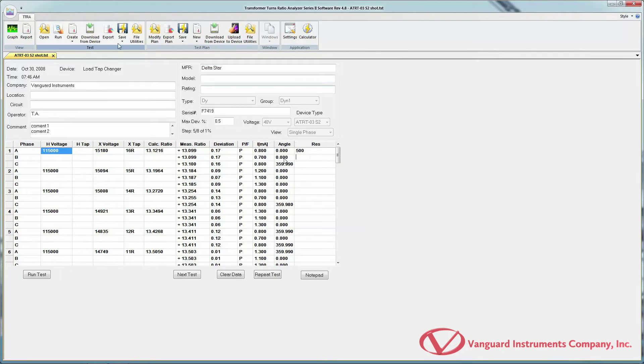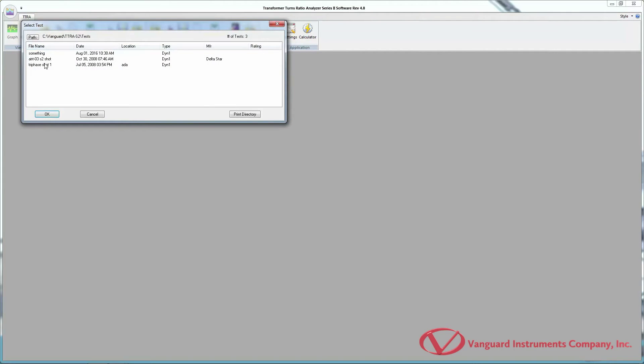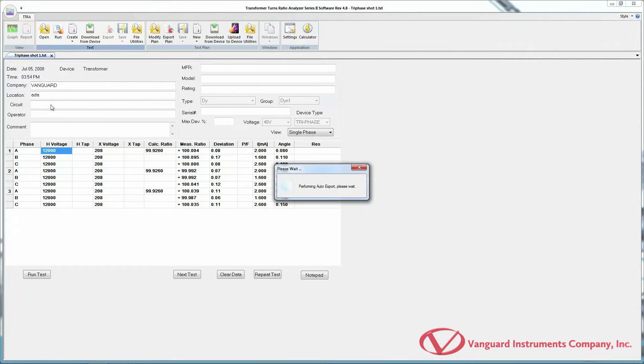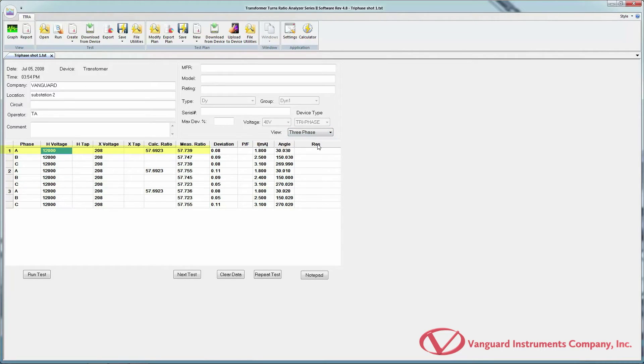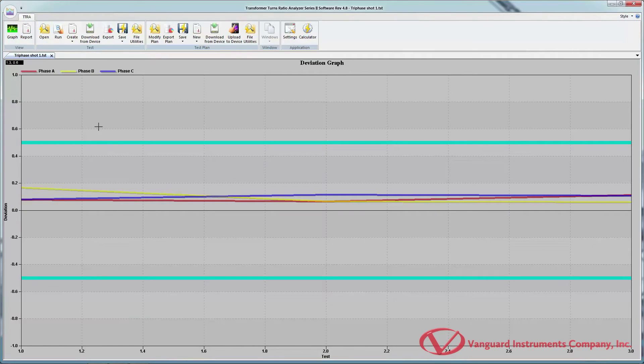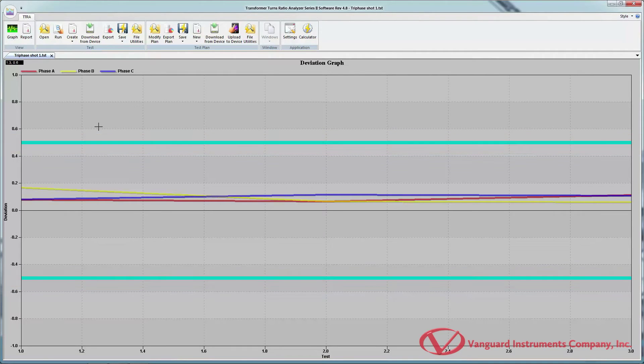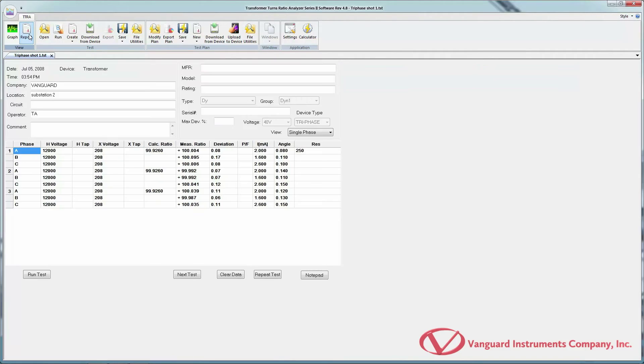If you want to manually export the test report at any point, you can click on the export icon. Let's open a test record from a transformer tested with the Vanguard TriPhase true three-phase turns ratio tester. When viewing a test record from the TriPhase, you have the option to view data in single-phase or three-phase mode. In single-phase mode, the turns ratio is calculated using the line-to-neutral calculation method based on the transformer type. In three-phase mode, the turns ratio is simply the H voltage divided by the X voltage. You can view the deviation graph by clicking the graph icon in the View command group; it shows test record number on the X-axis and deviation percentage on the Y-axis, with cyan bands showing a standard deviation of 0.5%.